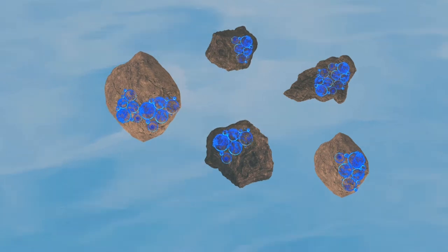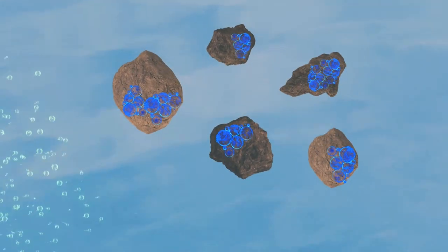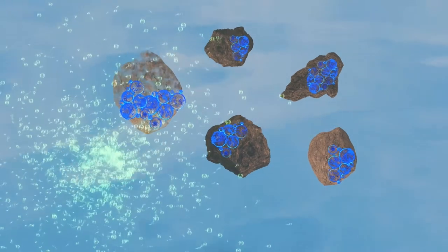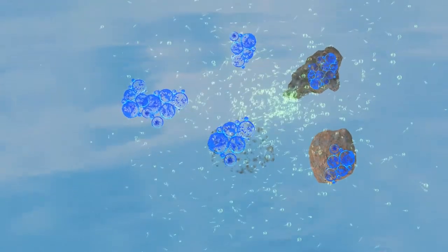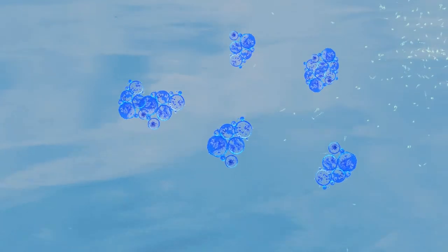If small suspended solids are not removed from the condenser water system, they will reduce the effectiveness of oxidizing agents in reducing bacteria. As you can see, as the biocide moves over the particulates harboring the bacteria, it oxidizes the particulates, and then there is not enough chemical left to kill the bacteria.